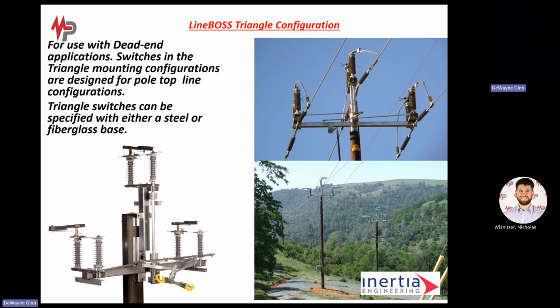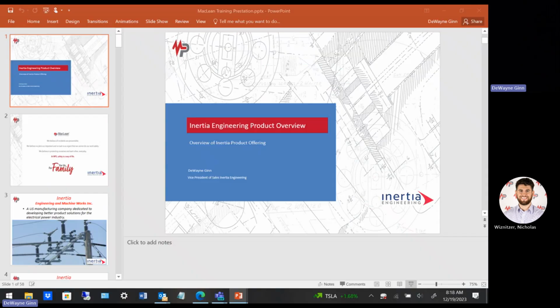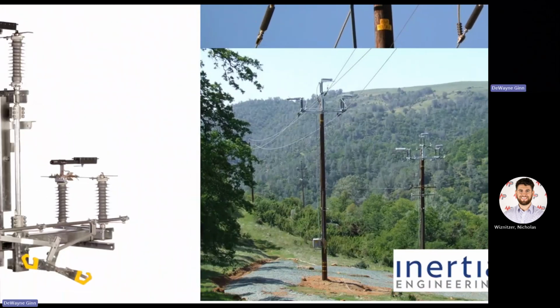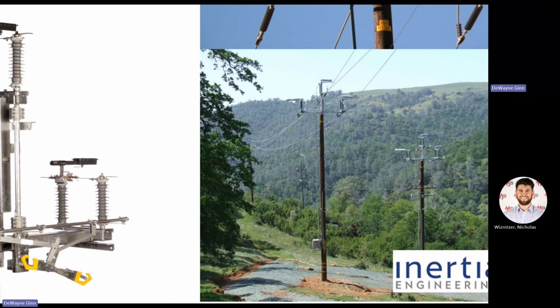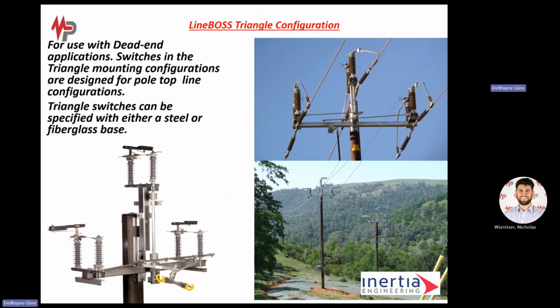Delta configuration of pole mount. It's on top of a pole. It depends on how they have their conductor run. This one has a static wire on top of it. I'm going to blow this up and show you that's a motor operator on that pole. That's sitting 10 feet off the ground. It's for a snowpack that goes up in here. This is in the Sierra Nevada, so consequently, snow gets up to it. It keeps it from being covered up in the snow base at that point.